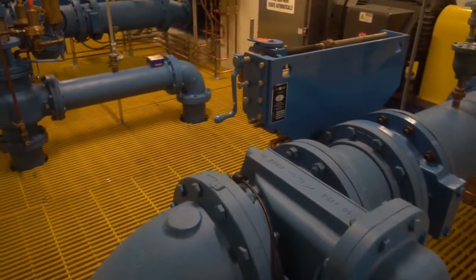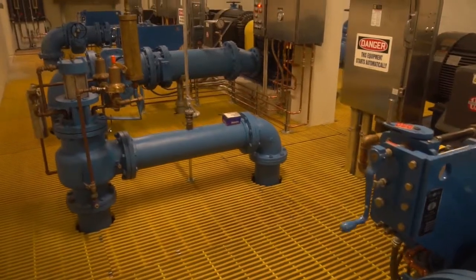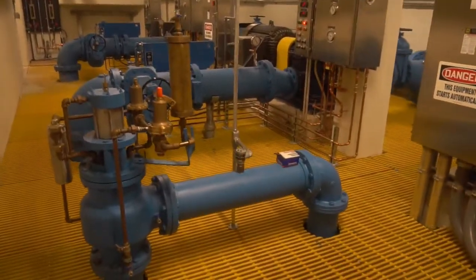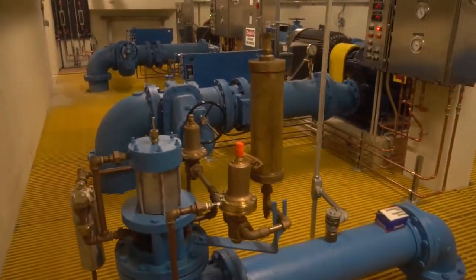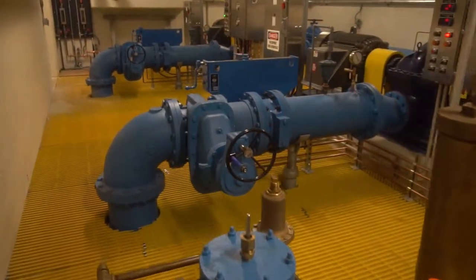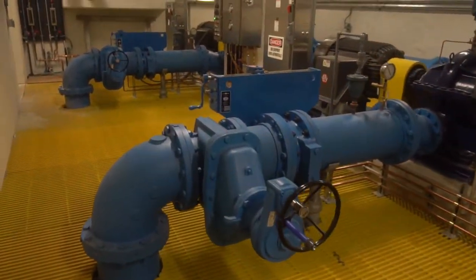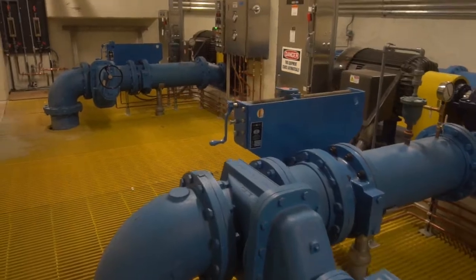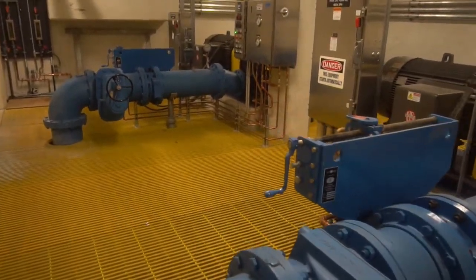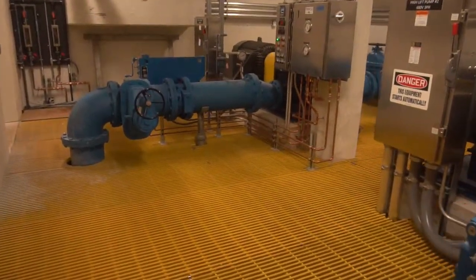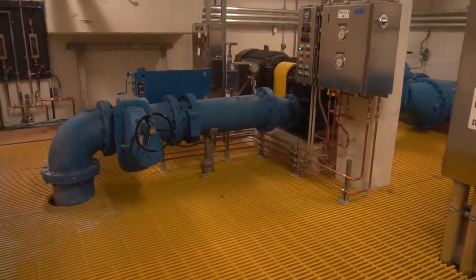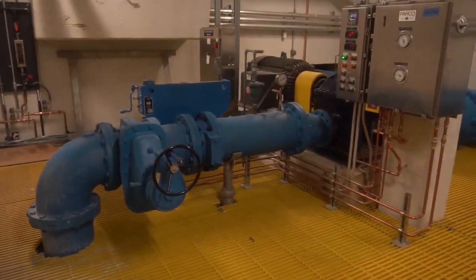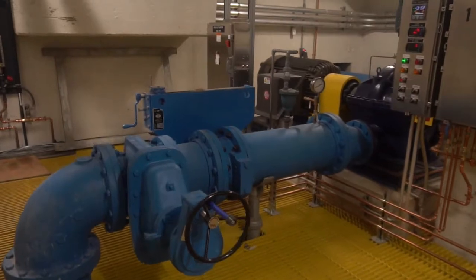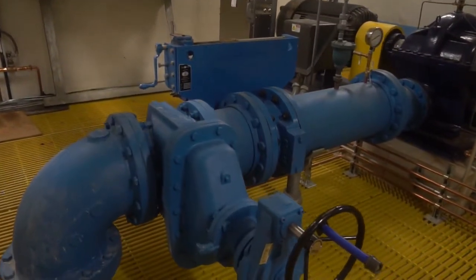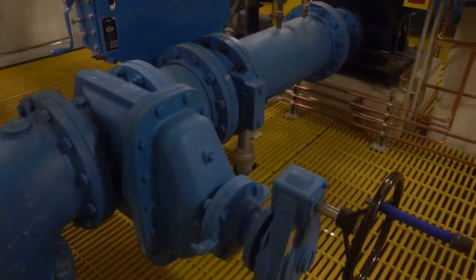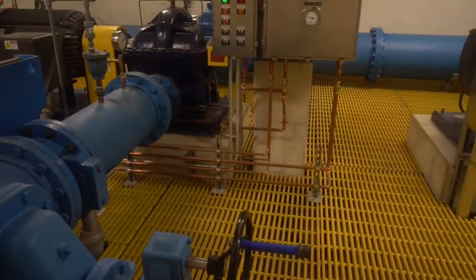This is the new high lift pump room, which was actually part of phase 2 of the project. These 3 pumps, each rated at 6 million gallons a day, operate off of VFDs from the electrical room and can be viewed and controlled locally and from SCADA. They all have surge control equipment as well as manual operators so that we can service the units.